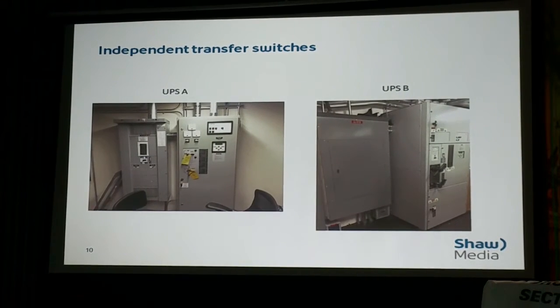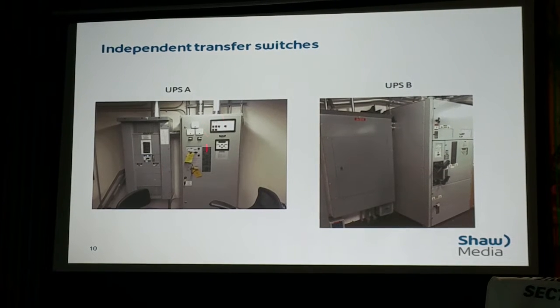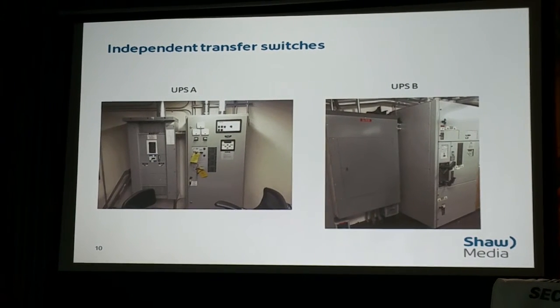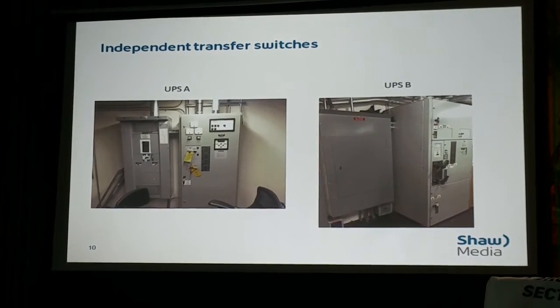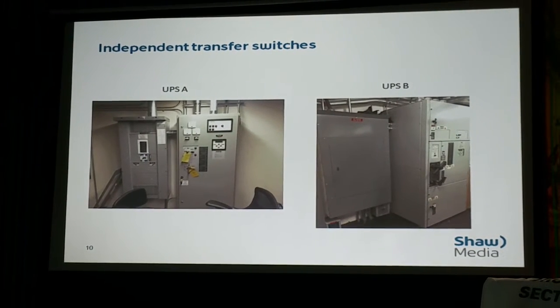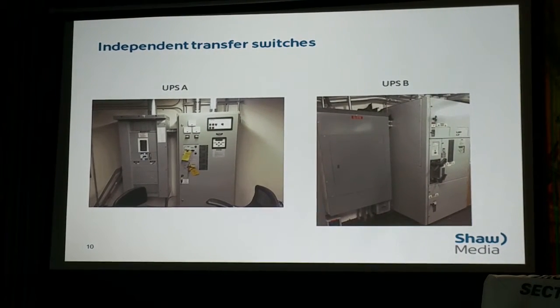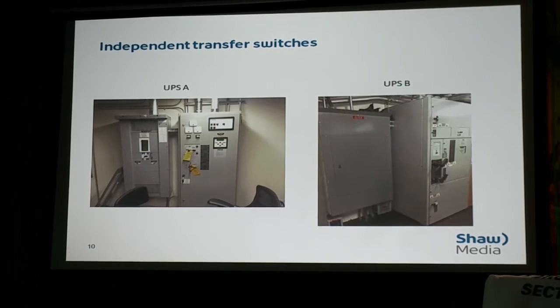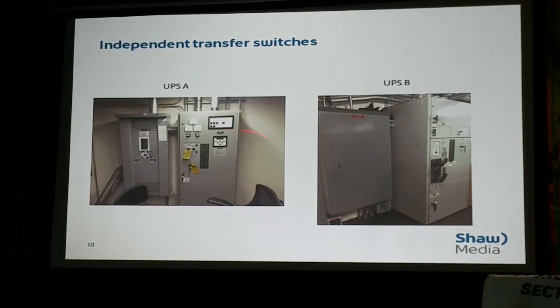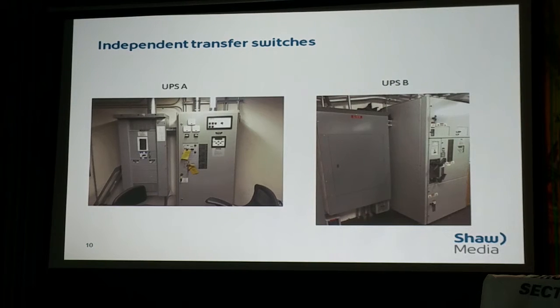These are the little transfer switches, and their job is to bring up the diesel generator when it's time to switch over. There's one for A and one for B, and they're actually timed slightly differently so they don't both take the load onto the generator at the same time.